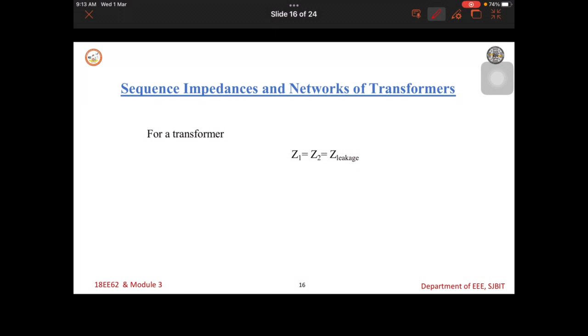Suppose you take a two winding transformer of this kind. The windings of the primary and the secondary on a three phase basis may be connected in different fashions: star star, star delta, delta star, star grounded, like this, many combinations. There are 9 combinations we can make. So for all these different winding connections of primary and secondary windings, let us understand how to write the zero sequence network.